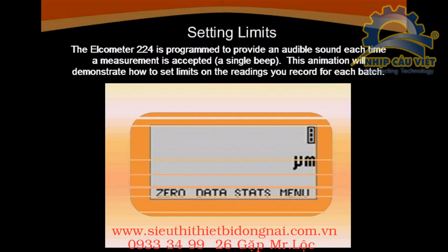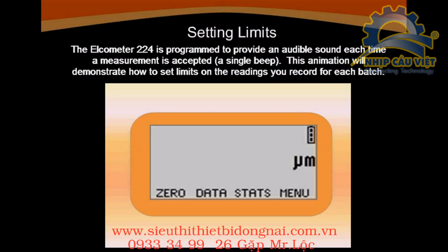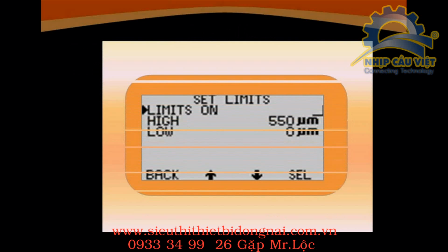The first step in defining your reading limits is selecting the data option from your main LCD display. Remember that the 224 is equipped with an audible alarm which will notify you if a reading should fall outside your limit. Arrow down to set limits and press. Let's start with the lower reading boundary first. Arrow down to low, and press the select key.